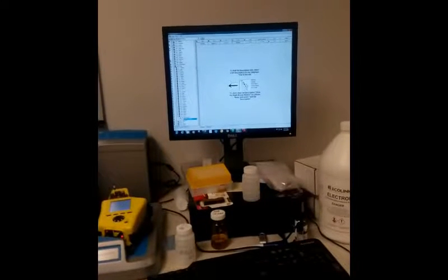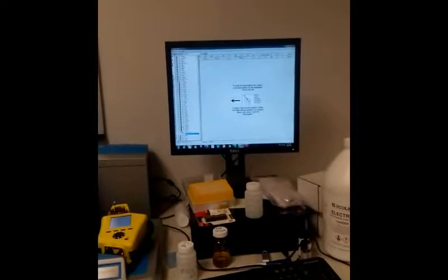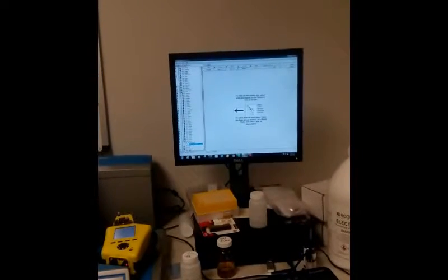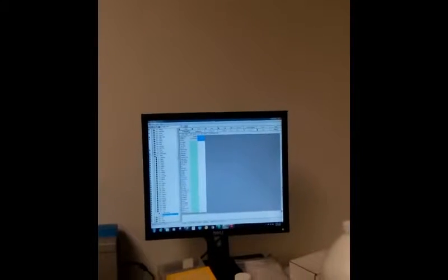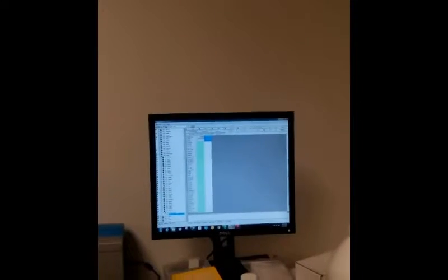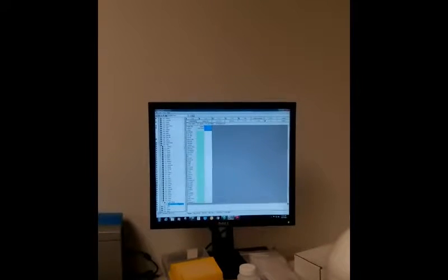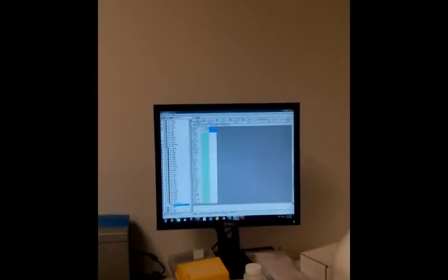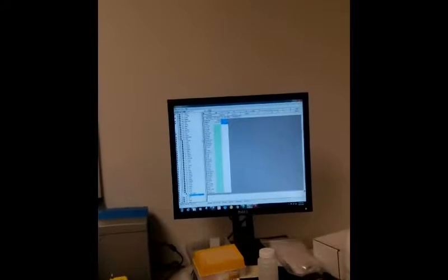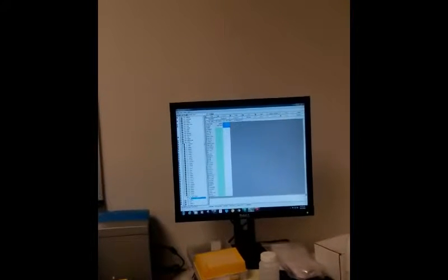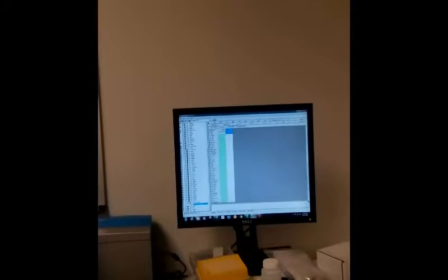Now, this is what you're going to be referencing against. So once you're in there, it should be a reference oil. It should be a fresh oil. Typically for fluid scans, we recommend that you always go ahead and create your own user fluids. So ideally, they should always be new fluids. So if I create my own user fluid, I get my new substance ID in there. It will be assigned automatically, or I'll have to assign it.